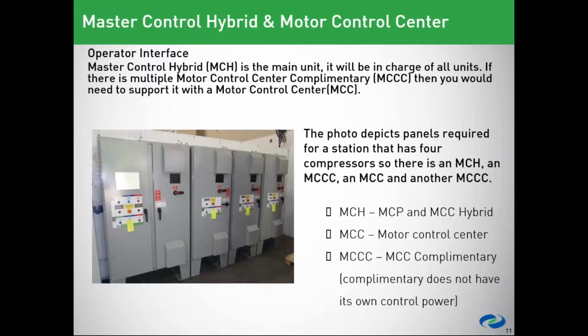It is the main unit. It has the HMI on it, and this will supply power for the next Motor Control Center complementary. So this is a basic unit that does not have its own control power applied to it. So the MCH will supply the power to that MCCC. The next unit in that line is an MCC, which does have a transformer in it to supply control power to it, and it will also supply that power over to the next MCCC in the line, and that makes up the four blocks we see in this photograph.